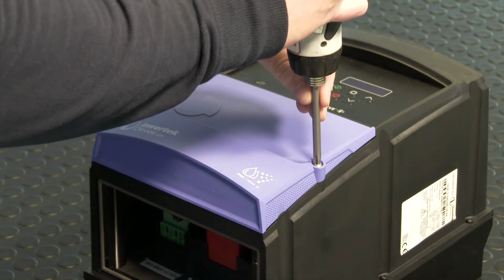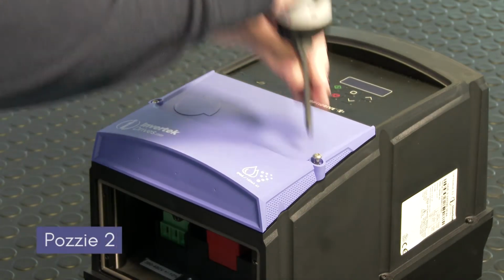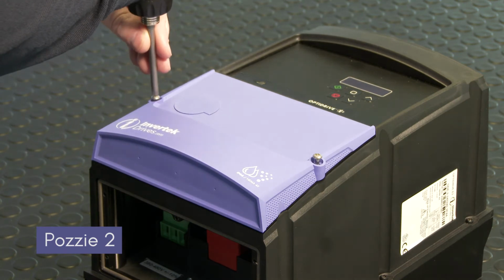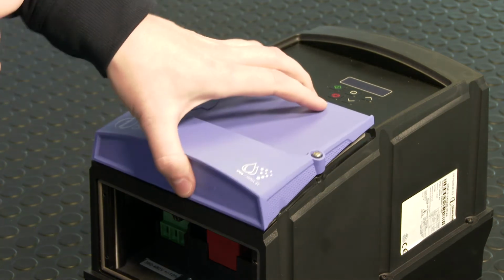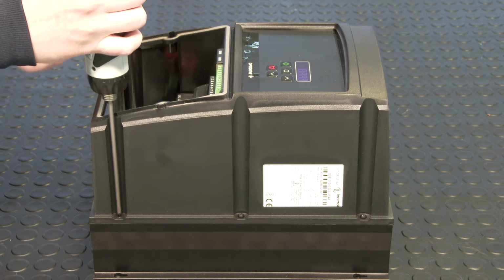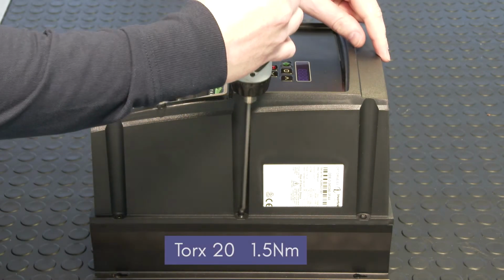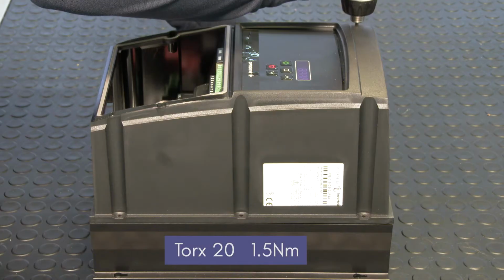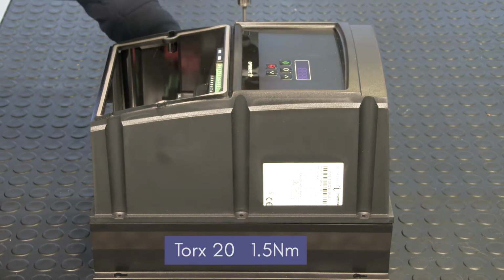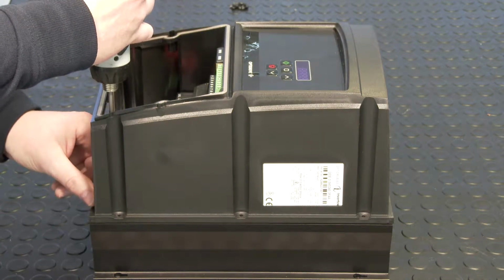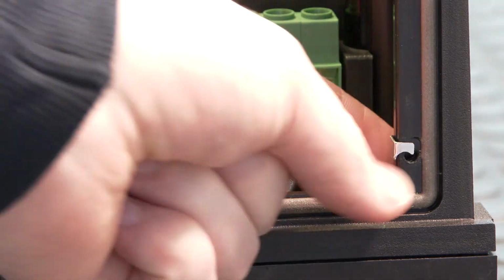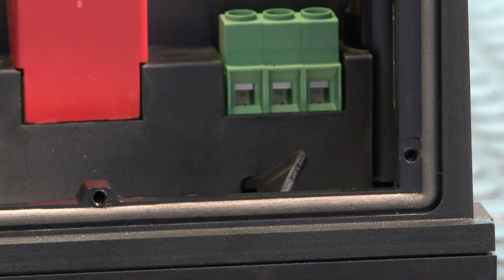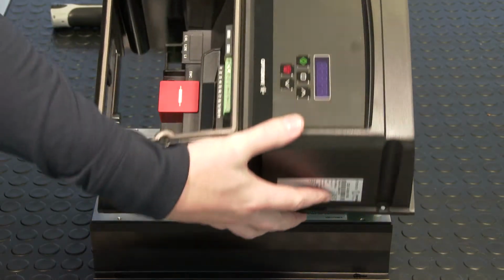To remove the control cover, use a Posi 2 screwdriver to loosen the 2 screws and lift the cover away. Using a Torx 20 screwdriver, remove the 6 cover screws and earth tab screw. The torque setting is 1.5 Nm. The cover can now be lifted away from the heatsink.